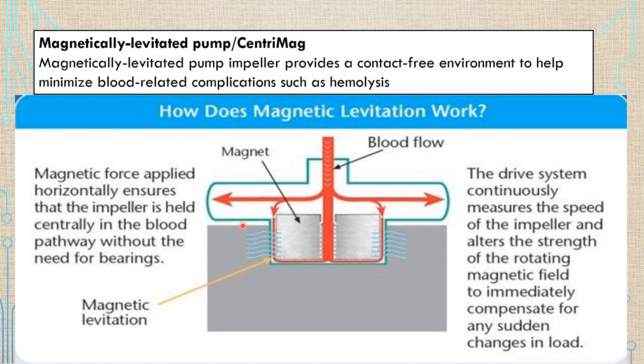The magnetically levitated pump uses magnetic force applied horizontally to ensure the impeller is held centrally in the blood, providing a contact-free environment to minimize blood-related complications such as hemolysis.